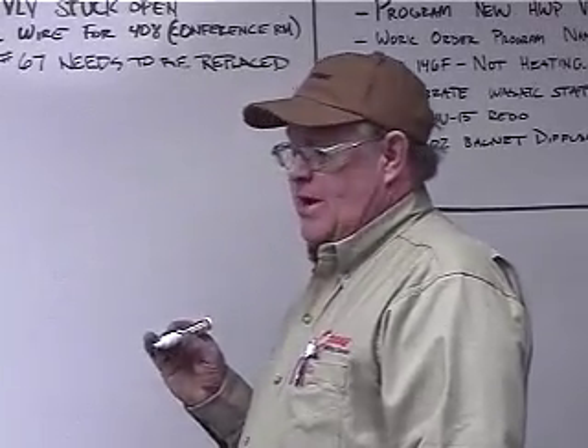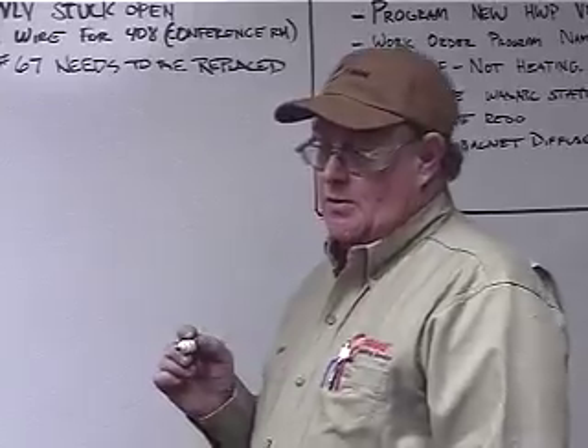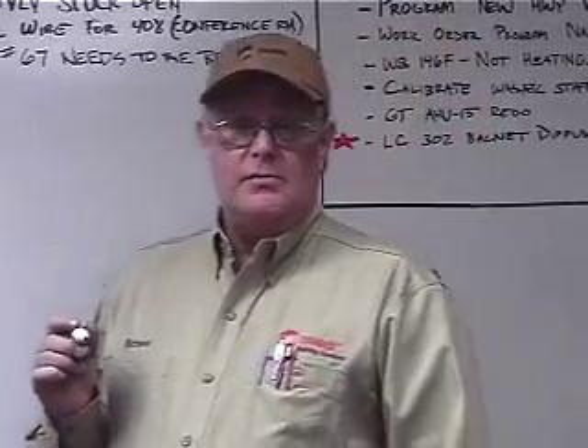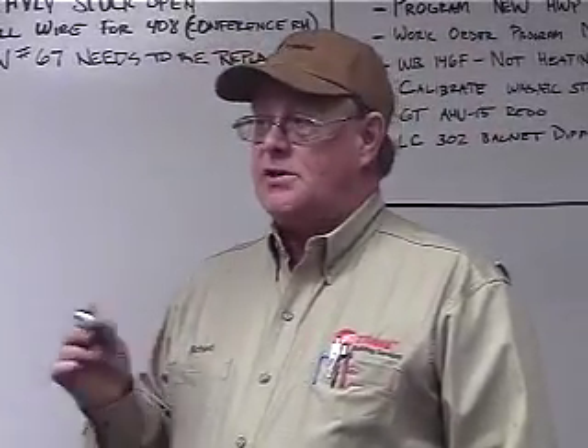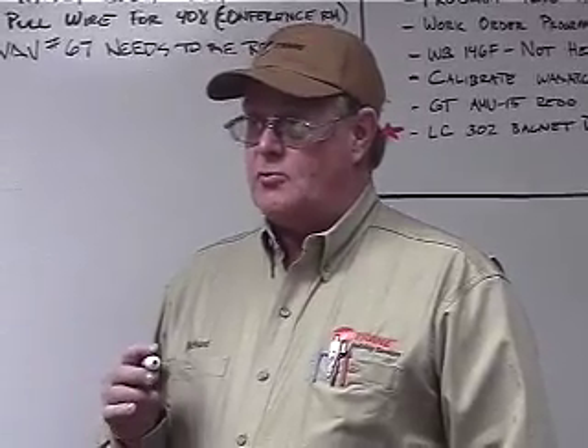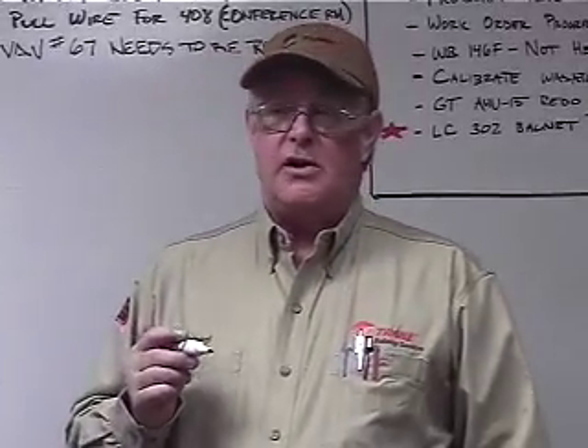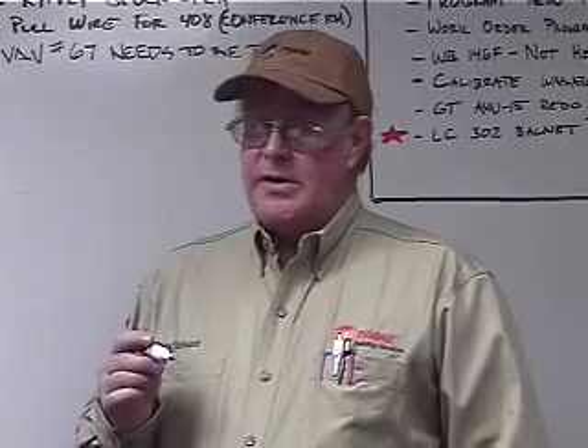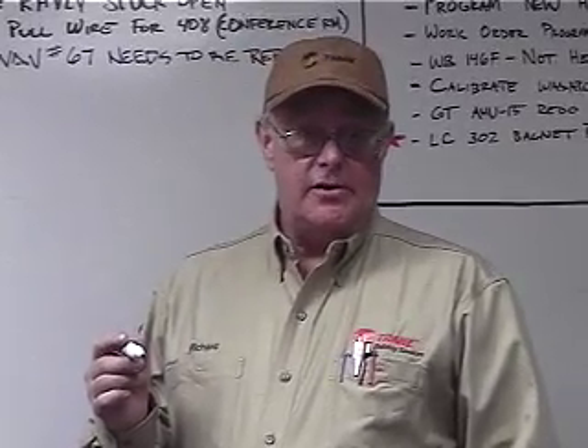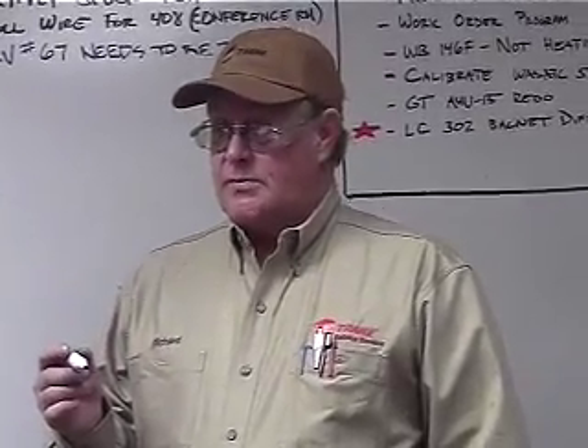As far as maintenance, basically what we like to do, Trane has taken a stand that we don't change the oil in the chillers every year anymore. What we do is we take an oil sample once a year, and we change the refrigerant filter and your oil filters.